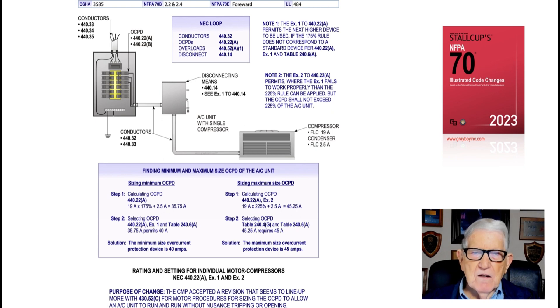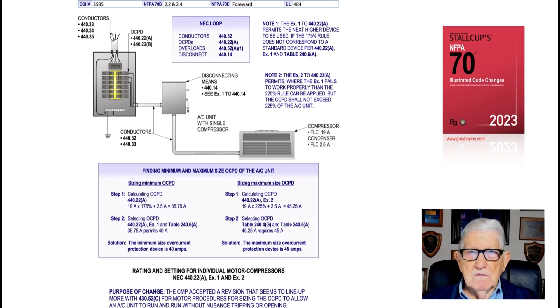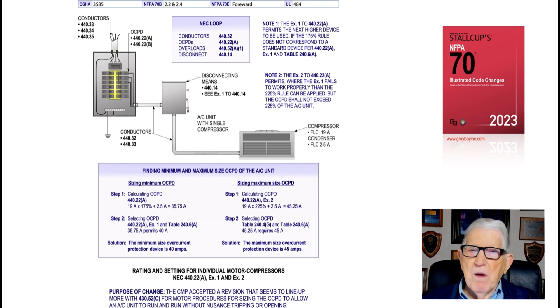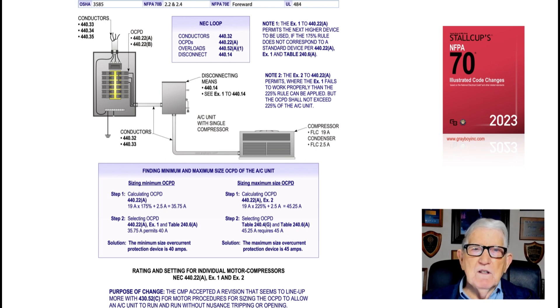This illustration deals with the rating and setting for an individual motor compressor in accordance with 440.22(A) Exception 1 and Exception 2. The purpose of the change was to let the user of the NEC know that you could raise the overcurrent device above 175% and even select it lower than 175%, but when you apply the 225% rule you'd have to round down — you couldn't round up. The calculation in the boxed information on the left shows you can round up above 175%, but using the 225% rule on the right, you cannot round up — you must round down. Notes 1 and 2 are letting you know you can do the same thing in section 440.22(A).